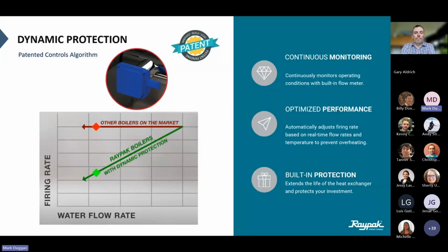We've got a minimum flow rate to fire the boiler, and we've got a minimum flow rate we need to meet for that boiler to run at 100% firing rate. And if we don't meet those, either the boiler will not fire, or it'll dial down its firing rate to meet the flow rate. I mentioned earlier that stainless steel in general is a pretty weak metal, even if we're using 316L stainless steel. And a lot of times you can either overheat or underheat that heat exchanger without really knowing it. So what that dynamic protection does is prevent thermal shock of the heat exchanger, prevent it from overheating or underheating, and ultimately extend the life of that heat exchanger.